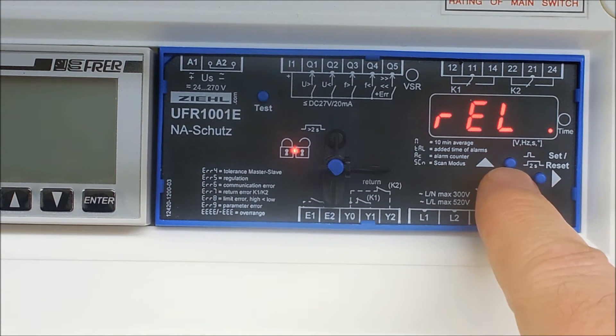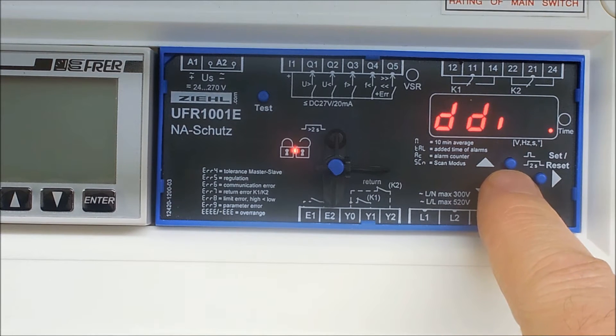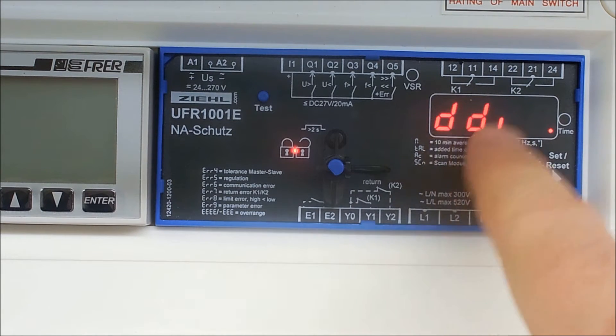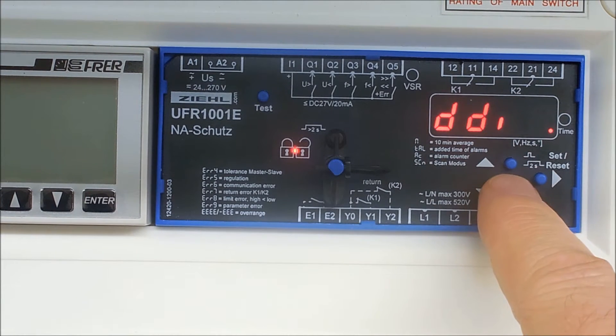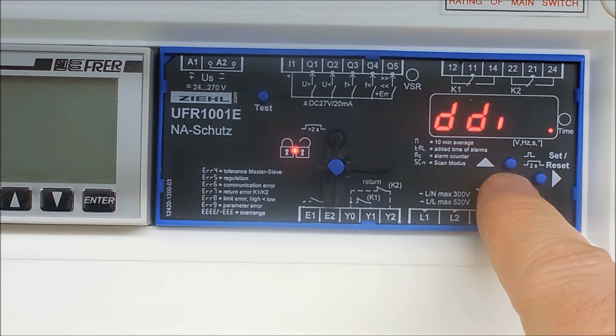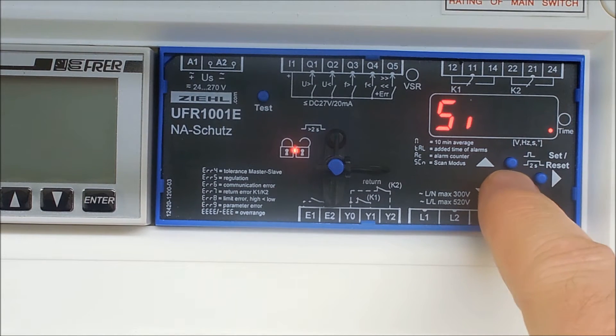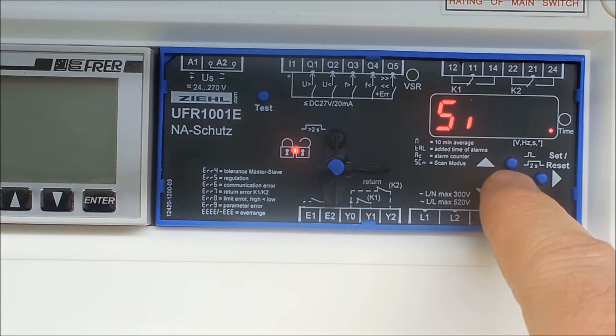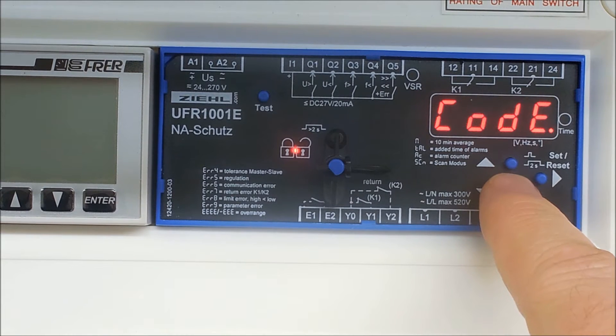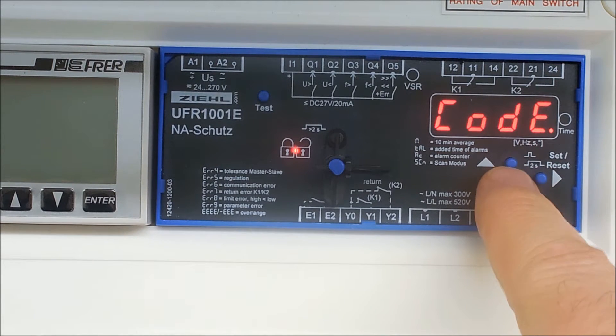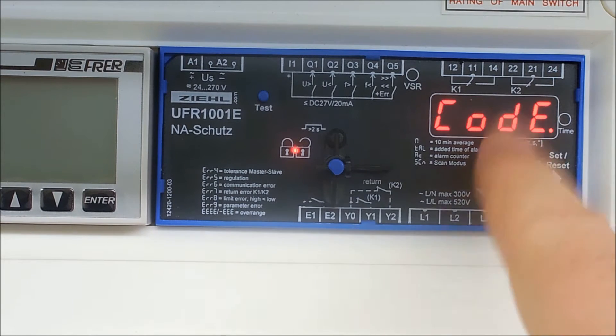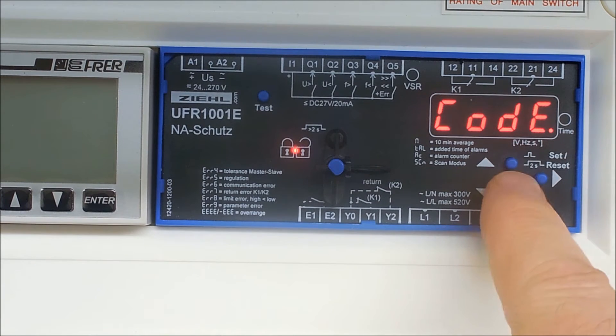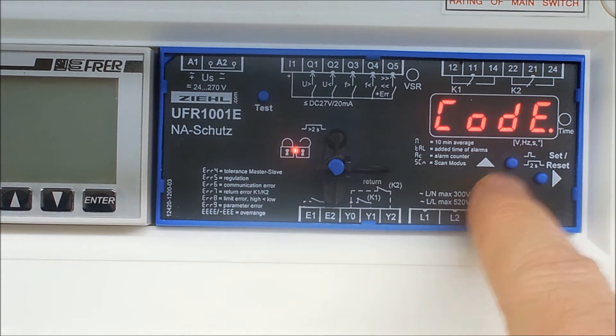You then have the relay for how the relays perform. You then have DDI which does do with the way the display updates and it's a personal thing to set those values. You have SI which is for simulation mode for voltage and frequency during self test. Then you have the code, the code is for factory reset if everything has gone drastically wrong. You have a code in the manual which you enter using that when this is unlocked which will allow you to recover the factory defaults.